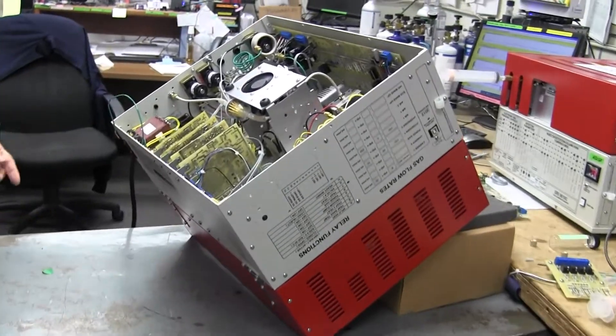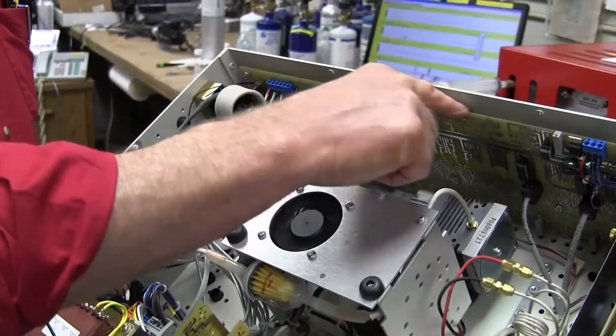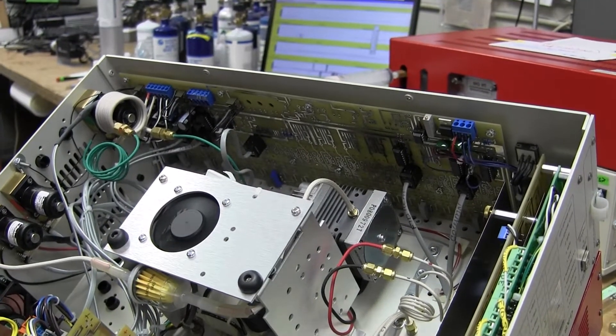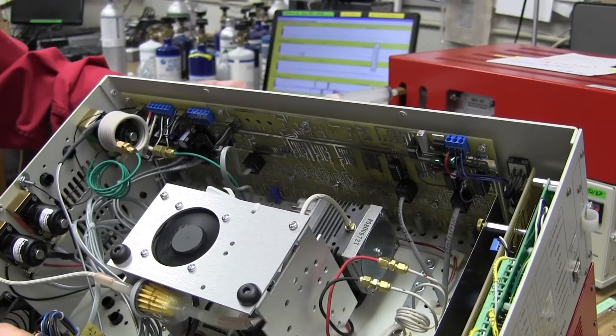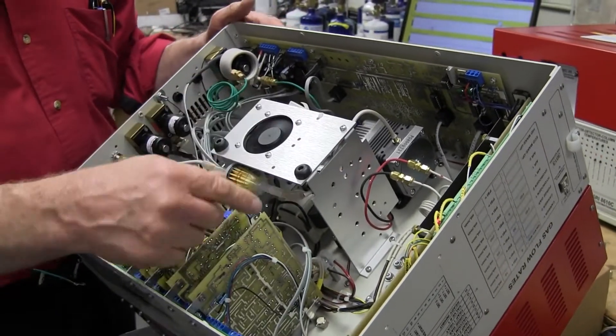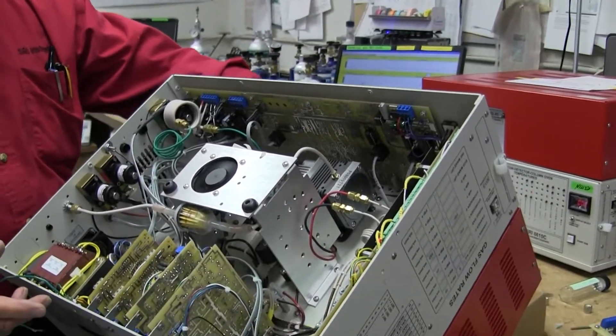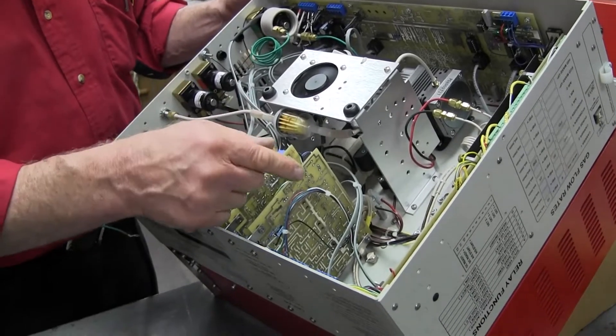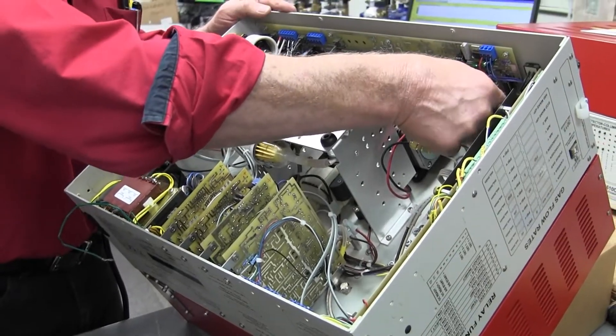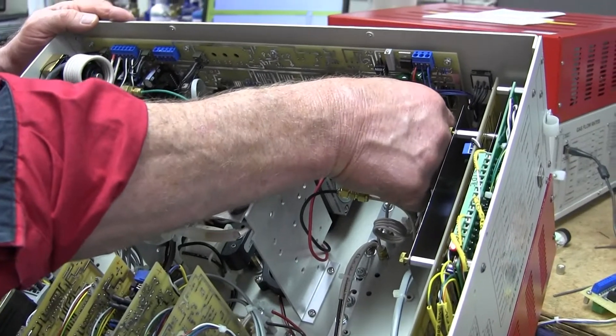So the thermocouple out-of-range alarm is located on the circuit board here on the front of the GC that we call the display board. And the display board gives you someplace to push a button so you can read the temperature of the oven and the various things that are hot. Sometimes there can be more than seven or eight different things that have to be at different temperatures. The way the information, which is just an analog voltage, gets from these circuit boards up to that is via these phone cords. So the phone cord is just like on the telephone at home. You just plug it in and it works.